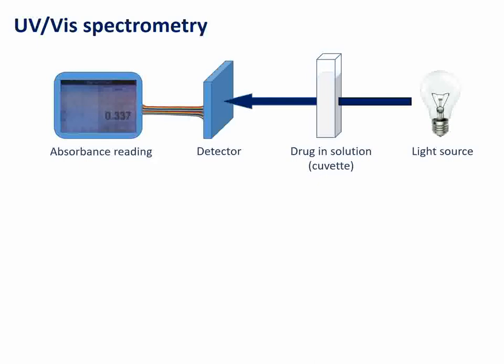The light source has something called a monochromator that the light will pass through, which enables you to fix the wavelength of light passing through the drug in solution — so you can be very specific that the light is only of a certain wavelength. The light beam passes through the drug in solution held in the UV cuvette, and the light which is able to permeate through reaches the detector, giving you an absorbance reading. The absorbance reading is in what we refer to as arbitrary units, so in terms of concentration it doesn't tell you that much directly.